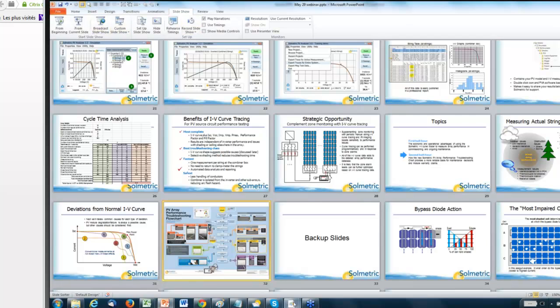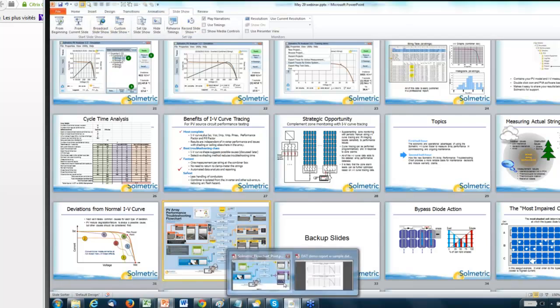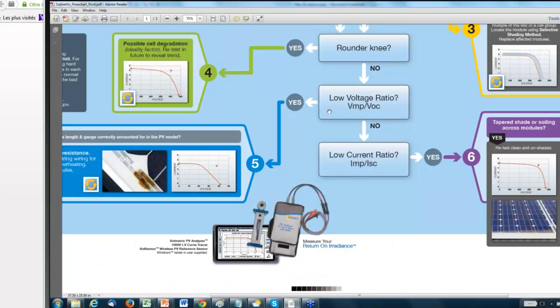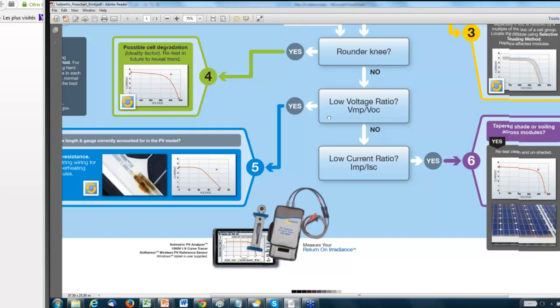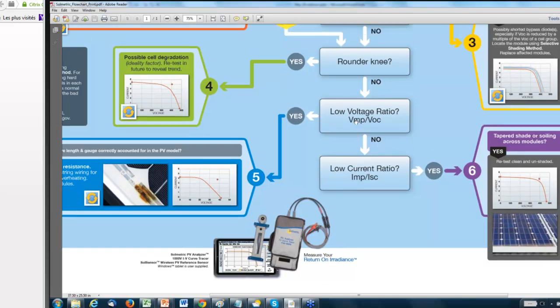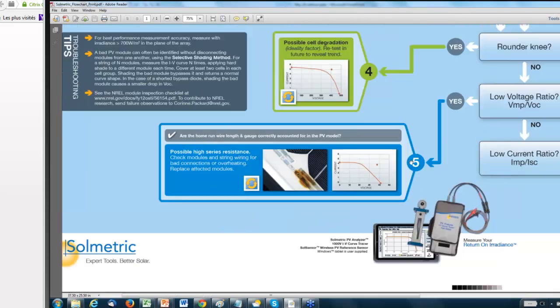Let's see. I want to be back in the flow chart. So that's what I mean by low voltage ratio. It means that your maximum power voltage is not as close to the VOC as it should be. It's shifted to the left. And so that's deviation number 5. And sure enough, you see in the IV curve here that in this measured curve, the knee of the curve is shifted way to the left of where it should be.